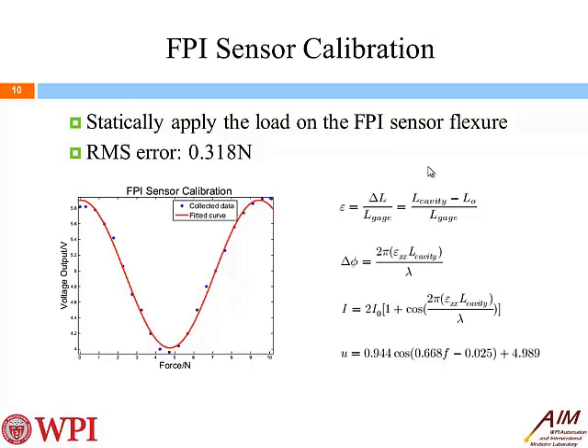The calibrated system can be shown in this voltage versus force graph. The blue dots represent actual measurements, and the red curve is the calibrated curve that fits into a sinusoidal function, which is the theoretical relationship between the force and the output voltage. So the root mean square error of this calibration is about 0.318 Newton.